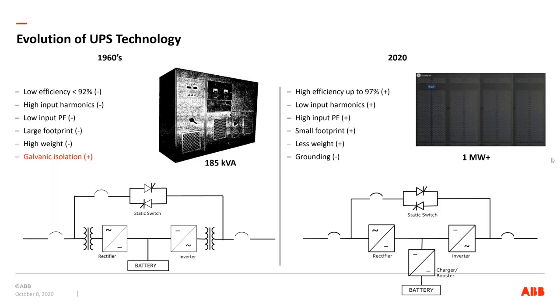I think there are actually still one or two manufacturers that do offer transformer-based UPSs, but they are going away. There's no doubt the vast majority of the market is transformerless today, primarily because of high efficiency, but obviously weight and footprint matter as well. But the last benefit that fans of transformer-based UPSs cite is galvanic isolation, which allows a transformer-based UPS to handle one extra failure mode that traditionally a transformerless UPS cannot. That's the reason I highlighted it here: a transformer-based UPS can handle a ground fault on the battery and still continue to function with no interruption. Traditionally, that's not possible with a transformerless UPS.